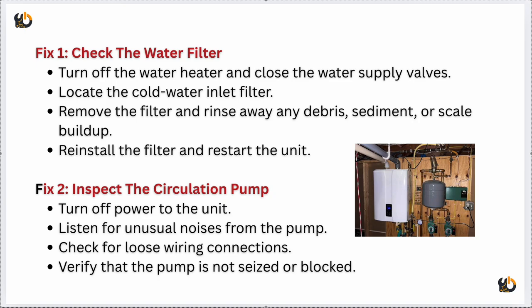Fix 2: inspect the circulation pump. So turn off power to the unit, listen for unusual noise from the pump, check for loose wiring connections, and verify that the pump is not seized or blocked.